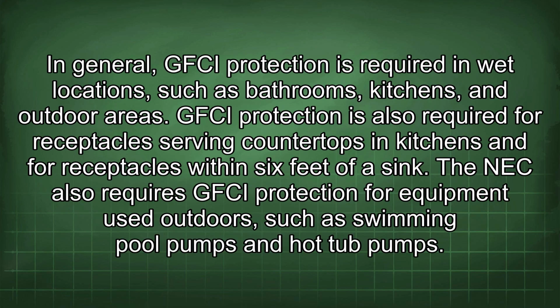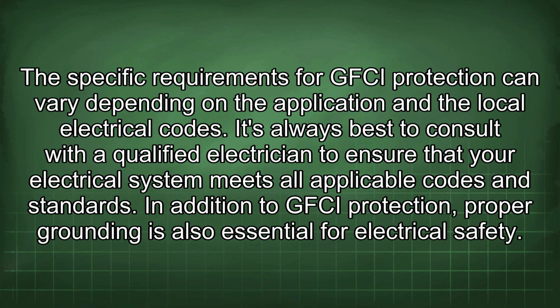In general, GFCI protection is required in wet locations such as bathrooms, kitchens, and outdoor areas. GFCI protection is also required for receptacles serving countertops in kitchens and for receptacles within 6 feet of a sink. The NEC also requires GFCI protection for equipment used outdoors, such as swimming pool pumps and hot tub pumps. The specific requirements for GFCI protection can vary depending on the application and the local electrical codes.